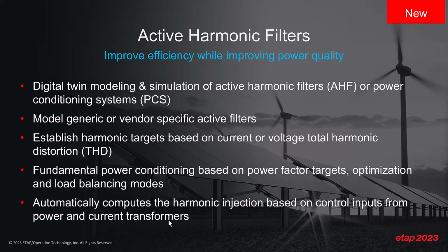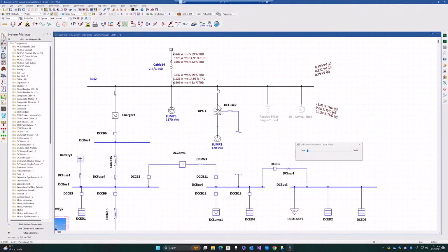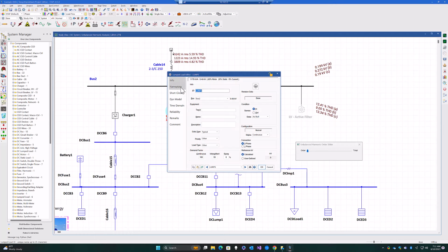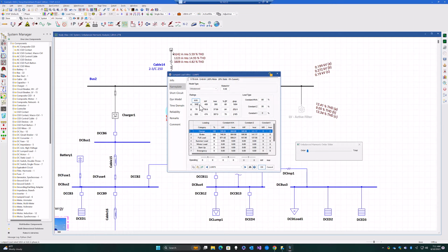So let's take the active harmonic filter, apply it to ETAP, and see how it works in action. Coming back to our file where we ran our unbalanced harmonic simulation, let's adjust this file a little bit so that we can see how our active filter works. But we'll first see how this active filter works in an unbalanced condition only for fundamental current.